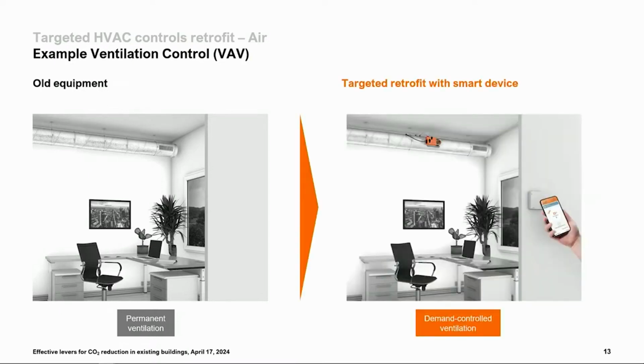So it's very simple. You need to measure the essential parameters. A CO2 sensor - nowadays very affordable. They used to be expensive, now they're really affordable. Measure the CO2 concentration: if nobody's in the room, low CO2 concentration. If people get into the room, it goes up, and the system opens to bring in more fresh air. A customer of ours just measured in his own office after a retrofit - he reduced the airflow by 60%, just with that simple measure.